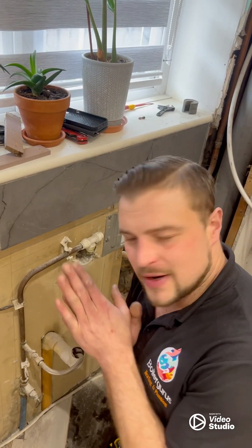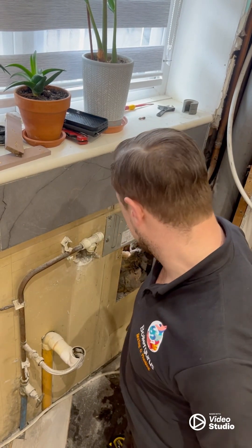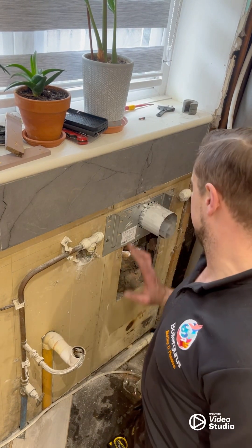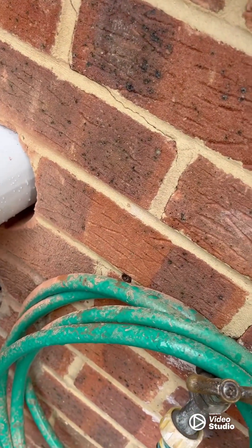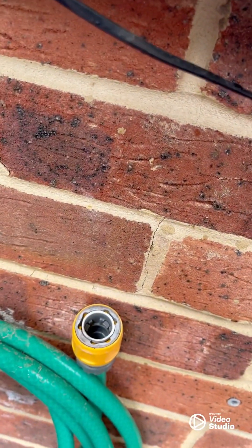Today we're fitting a Vaillant ecoTEC pure combi in this very awkward location in the kitchen unit. We're fitting it with a rear flue. We've got our bracket on the wall, we've put our flue through, and we're going to check the sides and put it in the right position.